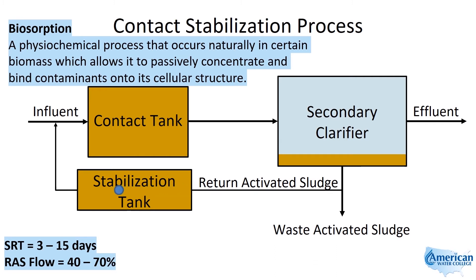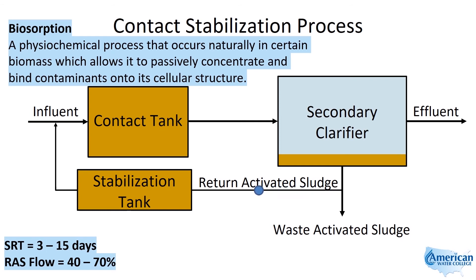This process is also advantageous in communities that have high I&I, or infiltration and inflow, in their collection systems, since the majority of the system solids are in the stabilization tank, which isn't impacted by the liquid flow stream. The solids retention time is in the range of 3 to 15 days, which is kind of an equivalent to your MCRT.